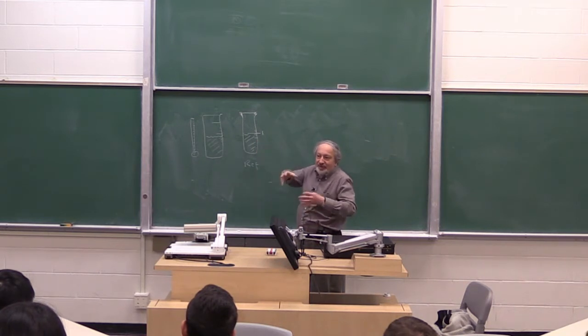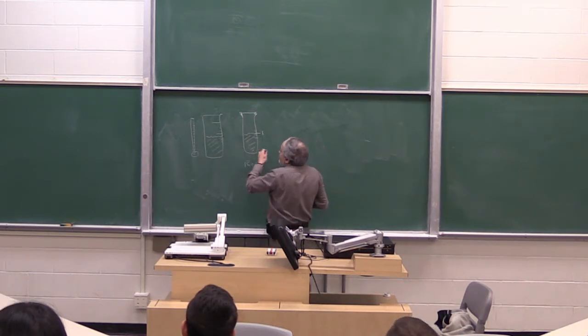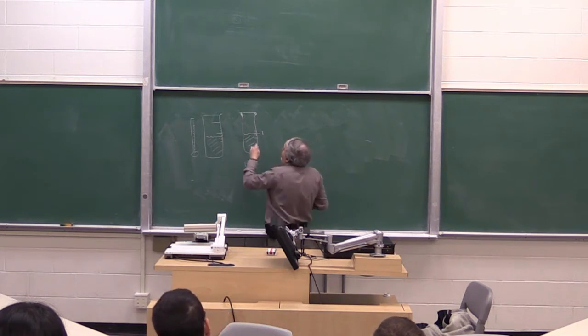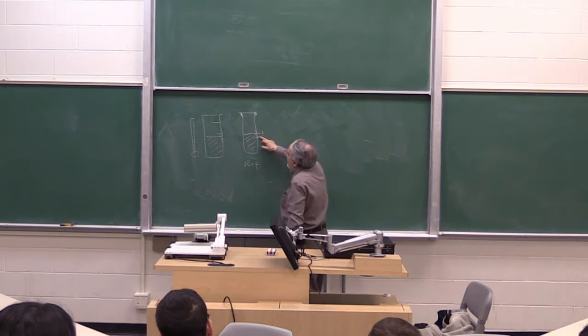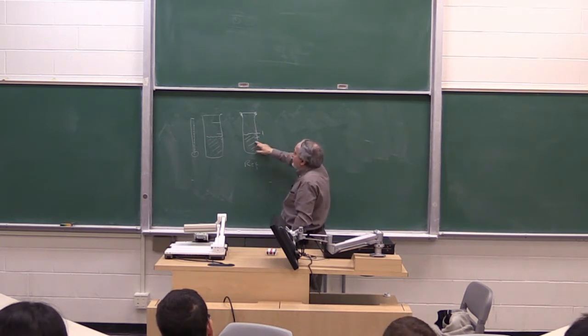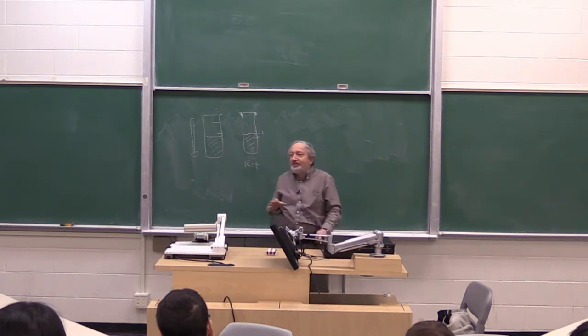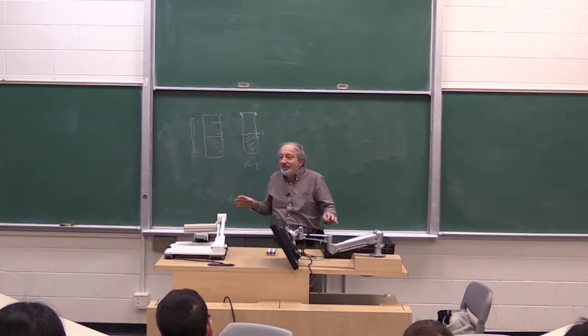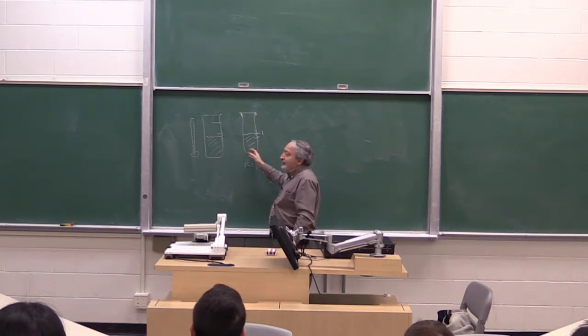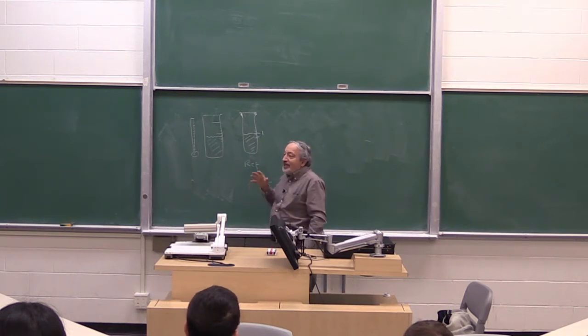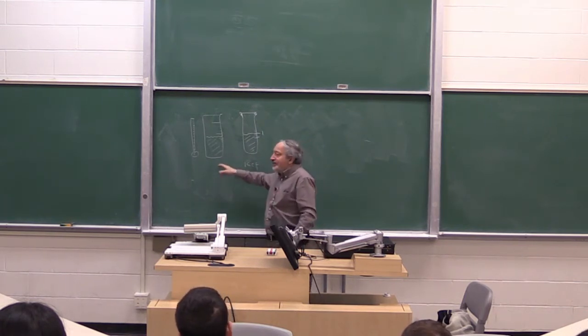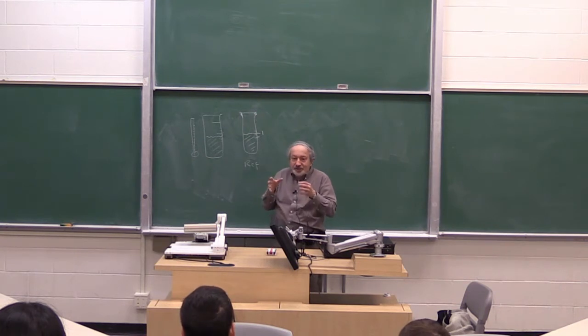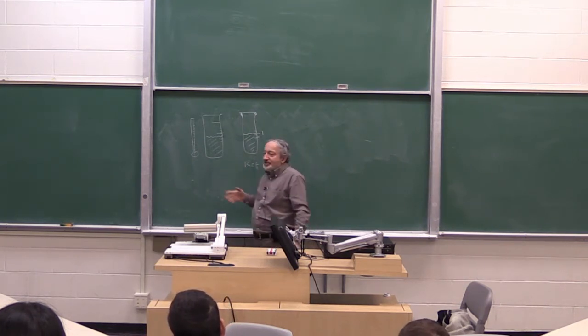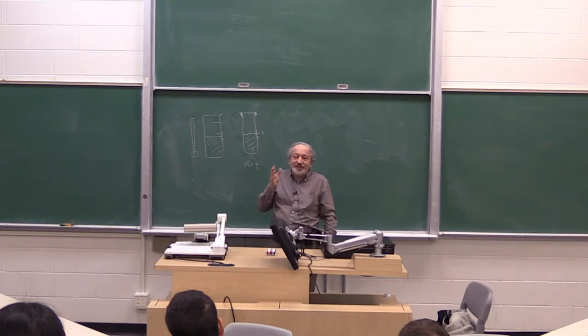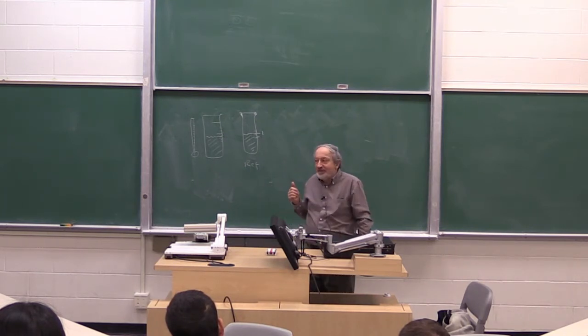Let's say because of temperature, the container, which is made of metal, increased, and so it reads a bit less. This gives you the correction factor, but it takes into account everything, even things you don't know. If air pressure affected it, if temperature affected it, if aging affected it, these two containers are identical, so if they change with age, most likely they change the same way. Even effects you can't think about will be taken care of.